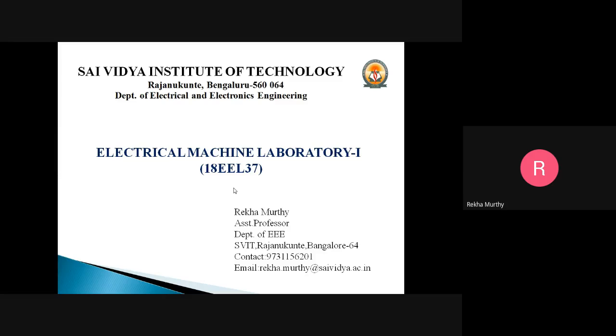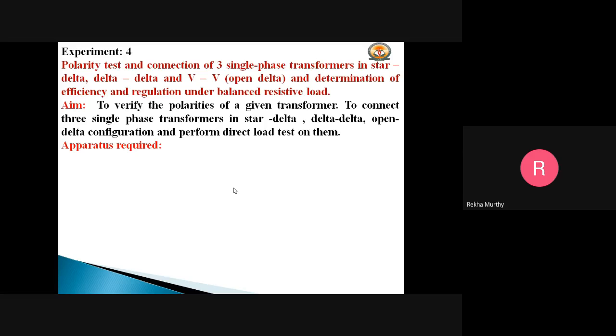Today I'm here to explain one of the cycle 1 experiments from the Electrical Machines Laboratory: the polarity test and connection of three single phase transformers in star-delta, delta-delta, and open delta (VV) configurations, and determination of efficiency and regulation under balanced resistive load.